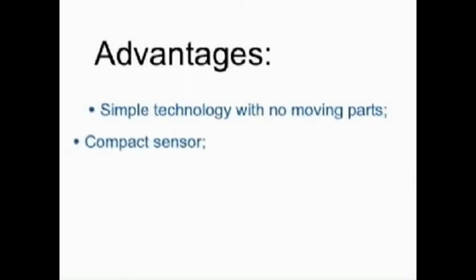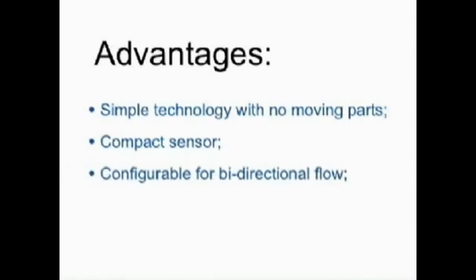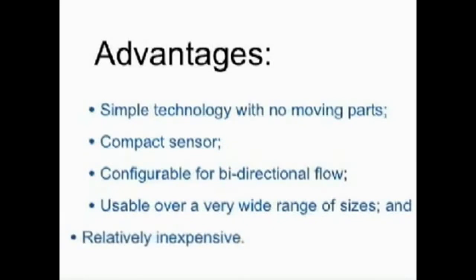There are many advantages to this approach. It's a simple technology with no moving parts. The flow measuring sensor can be very compact. Depending on the configuration of your pressure sensor, you can set it up for bidirectional flow. The approach is scalable over a very wide range of sizes and it's relatively inexpensive.